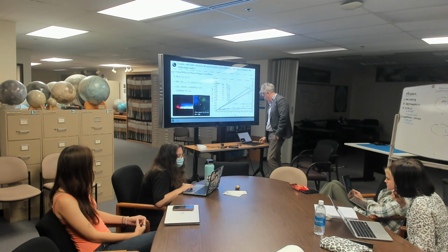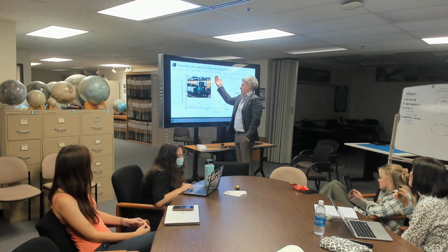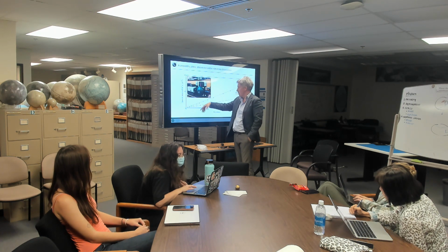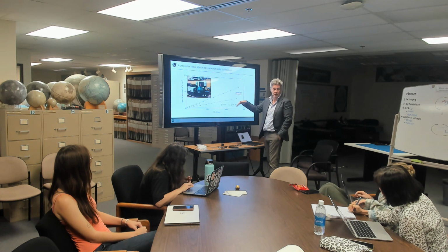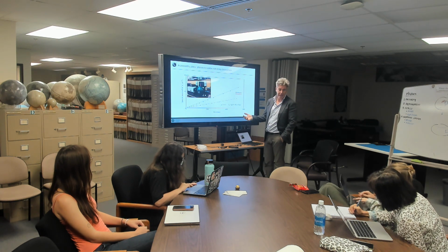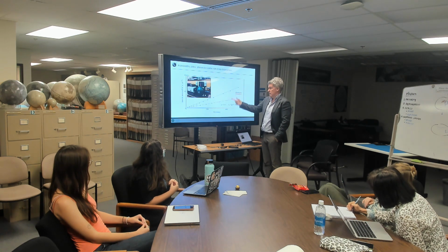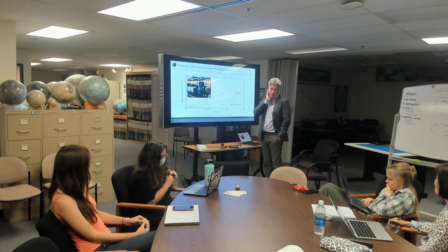And then to do the other wavelengths, there are a couple of ways I can do it. I could put a filter in here, or I could put a filter on the instrument itself, and then I could reproduce that measurement for a different wavelength and produce another regression equation that allows me to calibrate from DN to spectral radiance. But that's how easy that is. It's just calibration.